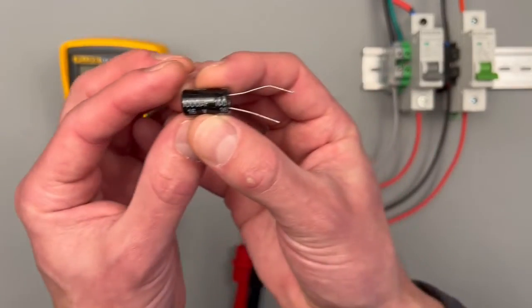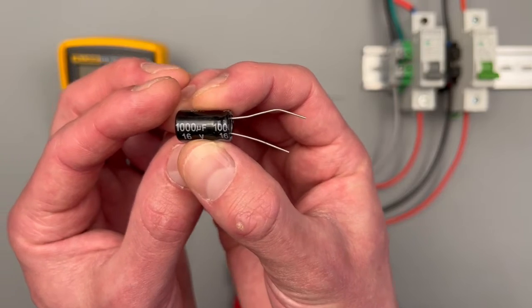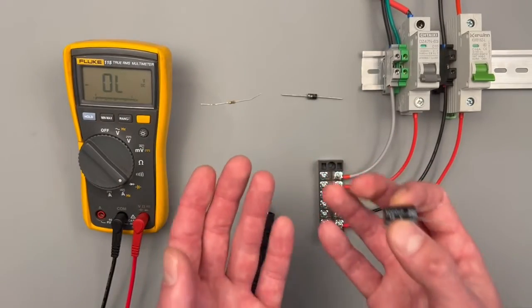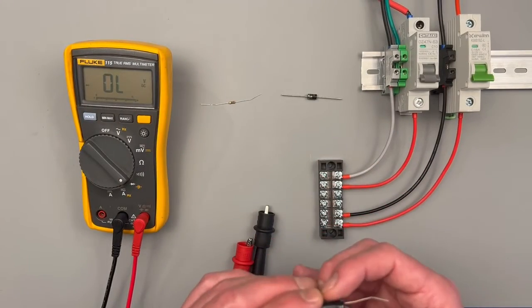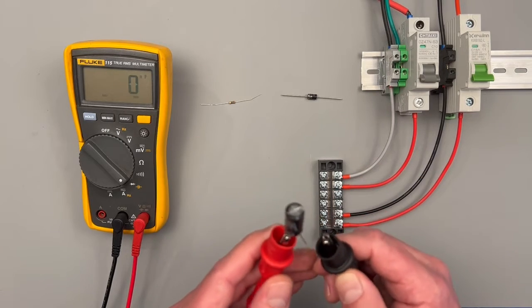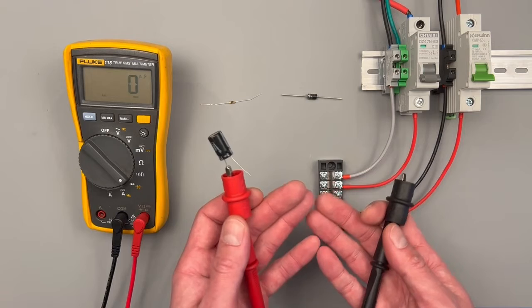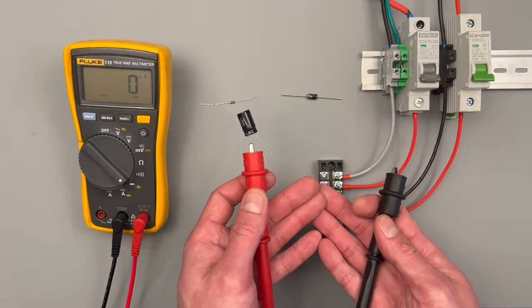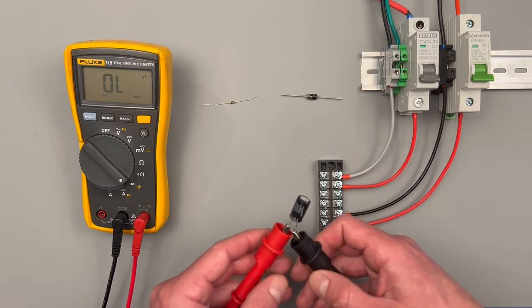Next is for capacitance. Again, it's in yellow indicating that we'll need to hit this yellow button to measure the capacitance. This capacitor is rated for a thousand microfarads. We want to see if this capacitor is capable of holding that much. You're going to go ahead and attach your leads to your capacitor after it's been discharged or you could hurt the meter.